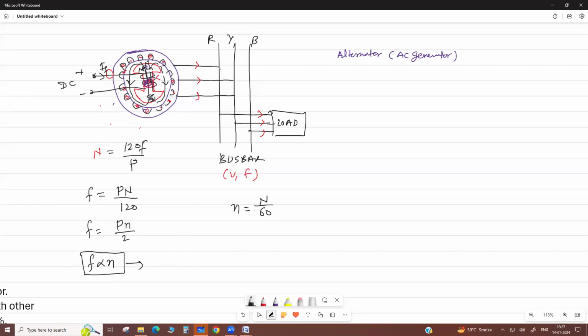And voltage induced, with this term voltage is directly proportional to flux, because generated induced EMF is directly proportional to phi, rate of change of flux. So actually voltage control means excitation control. So in alternator control, alternator control means we have two: one is voltage control, second is frequency control.